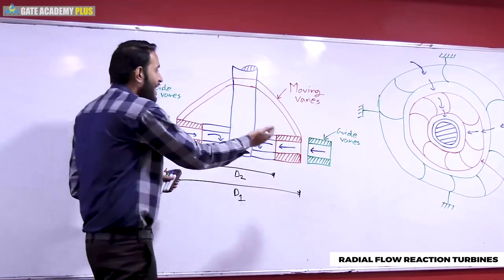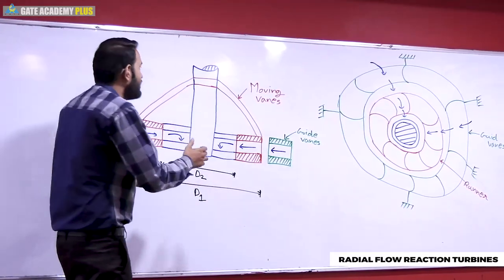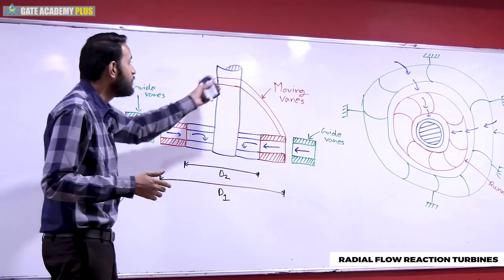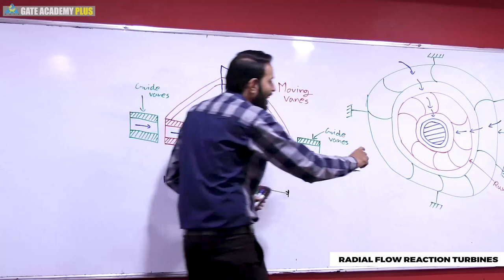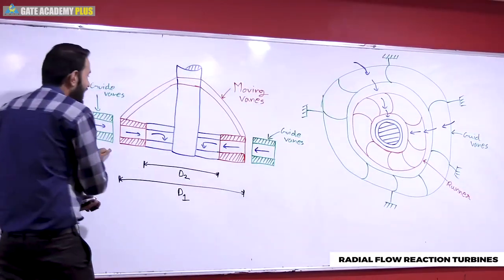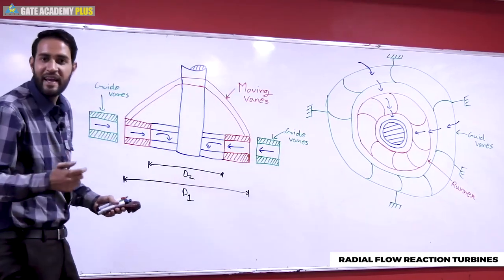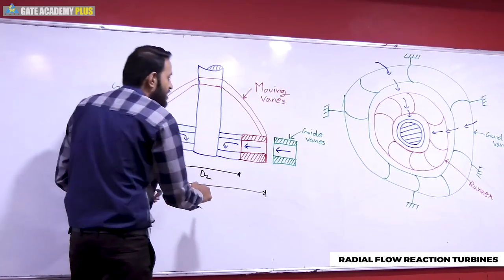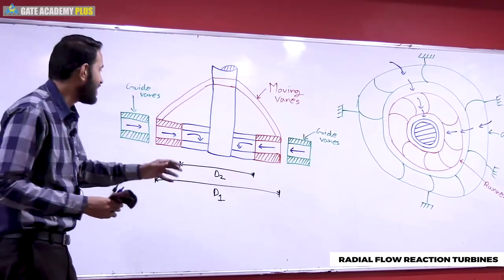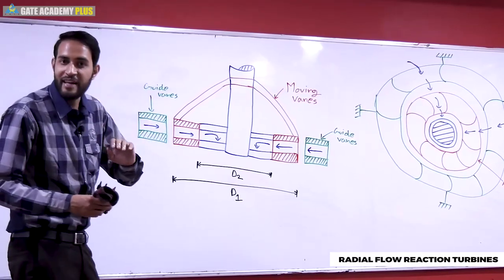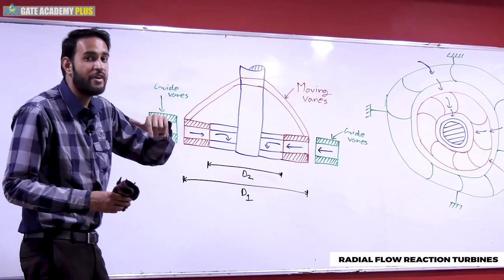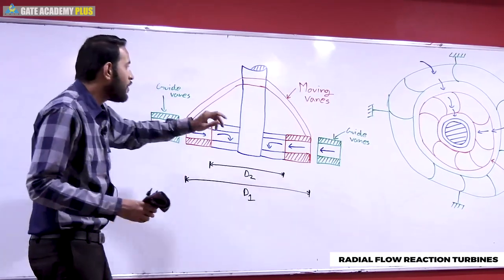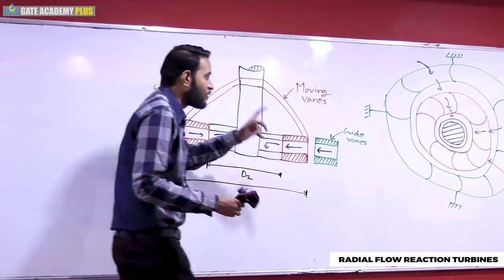We can see the side view: the shaft in the center, the runner with moving vanes, and the outer guide vanes which direct flow to the runner. Flow goes first through guide vanes, then moving vanes rotate, then discharge occurs. For numerical analysis, we know inlet and outlet tangential velocities using the expression VW1·U1 ± VW2·U2. We have two diameters D1 (outer) and D2 (inner) to calculate U1 and U2.